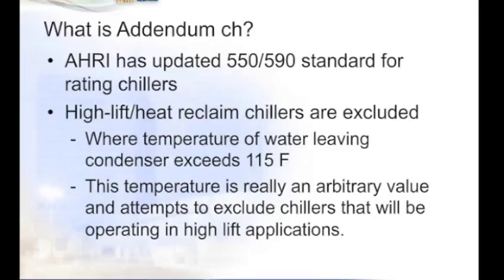And then as far as ASHRAE's definition of what the high lift applications might be, they're typically defined as condenser water leaving temperatures over 115 degrees. And then per ASHRAE's own commentary, this is really an arbitrary value and is attempting to exclude these chillers and high lift applications. We all design systems with leaving condenser water temperatures at a variety of temperatures. 115 degrees is typically outside a normal operating range, so that's an excellent cutoff point.